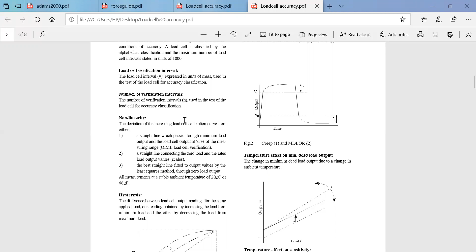And the last one is that all measurements at a stable ambient temperature should provide a consistent range. So you should be at room temperature, usually between 20 degrees Celsius to 34, yeah, 40 is the upper limit. You should get a proper measurement. There should not be any variation as such. Suppose at room temperature 30 it shows some value, and again at 34 degrees Celsius it shows some other value, then it is not right. It is fluctuating and very sensitive to even a small change in the environment. That should not happen. That will not happen also because the packaging plays a vital role here. Packaging is nothing but the protection device for the load cell which will be kept inside. Okay, so this is about the non-linearity aspect.